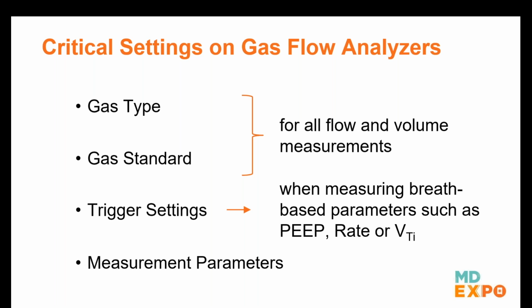Analyzers have a lot of different settings on them. Ventilators have a whole bunch of different settings on them. Sometimes they call the same thing by a different name. For example, you might have an analyzer that says breath rate on it, or just rate. And the ventilator you're testing may say frequency. And it means the same thing. It's still how many breaths per minute you're delivering. Same way with maybe peak inspiratory pressure. People familiar with that term? Right? Sometimes we call it PIP. On an analyzer, you might see it called P peak.